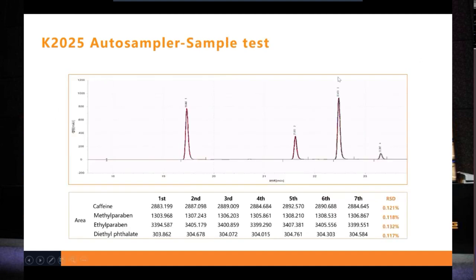We also did a test on the real samples, still the 4 standard samples. For the pump, the retention time, or RT, can be used to check the pump is good or not. But for the autosampler, the peak area is more related to the performance. So we use the area. The 4 standard samples have RSDs lower than 0.2%. All the RSDs are below 0.2% on a sequence of 7 rounds.